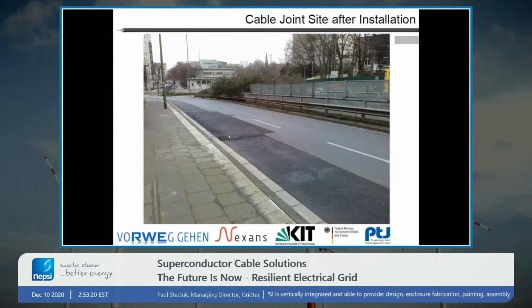The reason that they're allowed to pave over the splice box in superconductor cables is that, unlike conventional cables, you don't need to inspect these cables periodically. You can simply bury them and keep them operating. With conventional cables, they heat up and cool down every day. So when more current flows through the cables, they heat up and expand a little bit. And then at night, when the load drops off, they cool off and shrink a little bit. And over the years, that expansion and contraction eventually causes terminations and splices to fail.